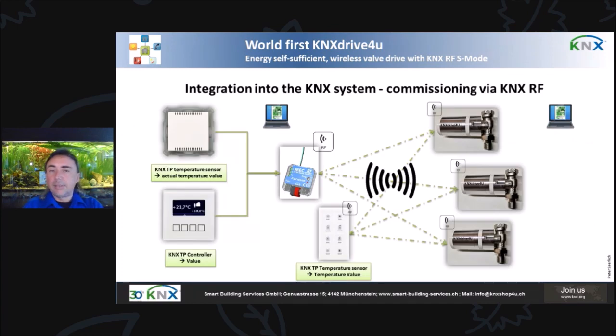So the integration in the KNX system is what I told you before. You have different ways - you can use the internal temperature sensor for your regulation, or you can use KNX RF devices that have a temperature sensor and go directly that way. You don't have to use any coupler.